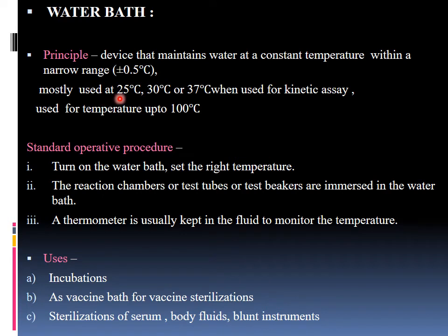Mostly used at 25 degrees Celsius, 30 degrees Celsius or 37 degrees Celsius when used for kinetic assays. Sometimes we use it for incubation also, like in Prothrombin test or APTT test, where we are using the water bath for incubation. So for such kinetic assays we will require 30, 37 or 25, and you can use it up to a highest temperature of 100 degrees centigrade, not more than that.